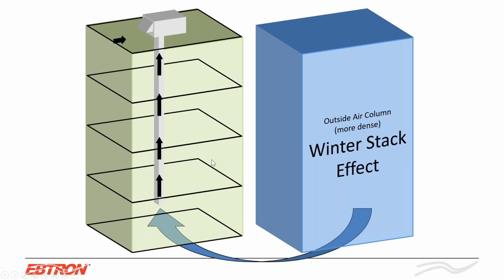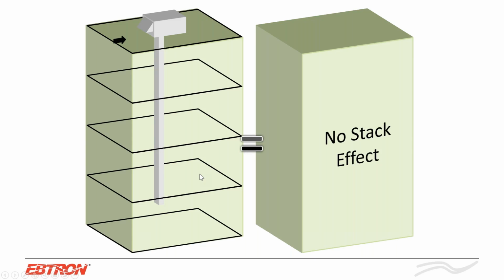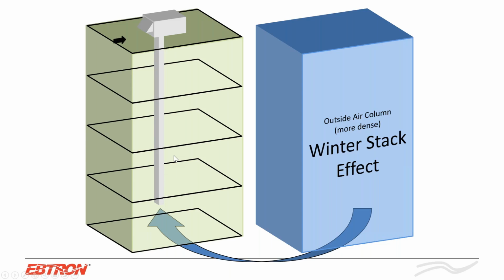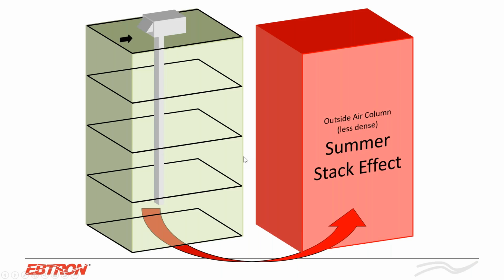Other issues that we see is stack effect. Normally, you want to maintain your building to be slightly positively pressurized to eliminate stack effect. Now, in the winter, for buildings greater than 4 stories, you'll have winter stack effect. What happens is you have a dense, colder column of air coming up through the bottom of the building, infiltrating your plenum, putting strain on the outside air being supplied to each space. You also have the same issue in the summer, where we call this reverse stack effect or summer stack effect. A lot of times, this is not as bad because the temperature differentials between your bottom floor and the top floors are not as bad.